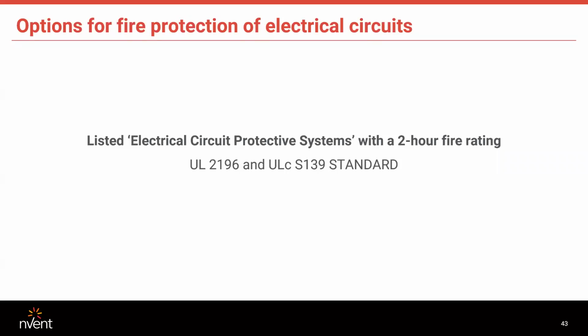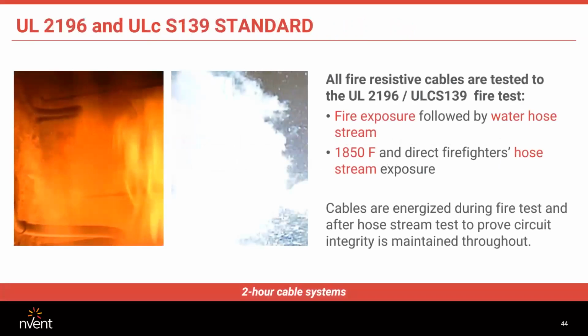So now, the best option, what I mentioned before, are the listed electrical circuit protective systems with a 2-hour rating, of course, which MI is one of them. And I will talk a little bit about the UL test. It's basically a 2-hour fire test, followed up by a water hose stream test, where the cable at the conclusion of the fire test is hit with a 30 PSI fire hose stream. Very powerful, enough to knock a person off their feet. And right before that test, the cables are disconnected. The power is disconnected for safety reasons. Then it's hit with the hose, and the cables are energized afterwards. And once it's been confirmed that circuit integrity has been maintained, your cable is deemed to have passed the test.